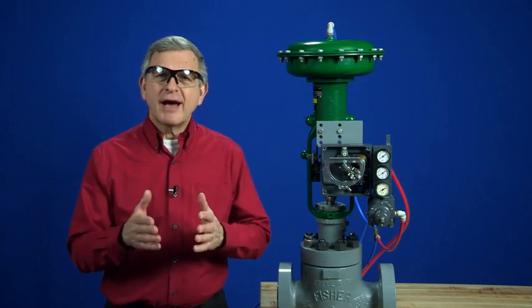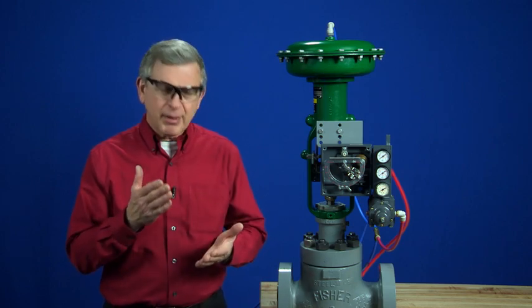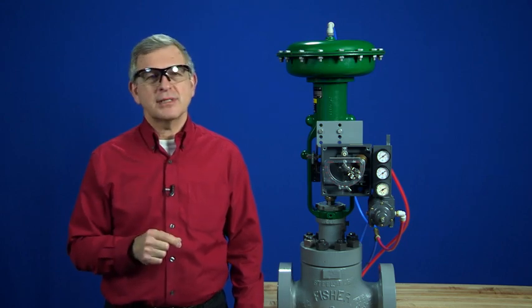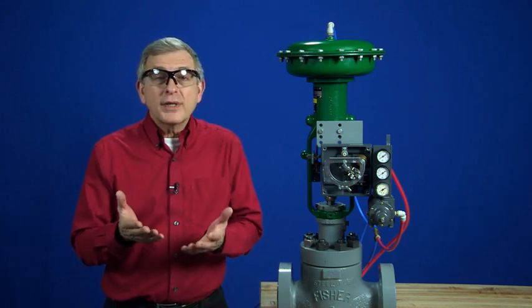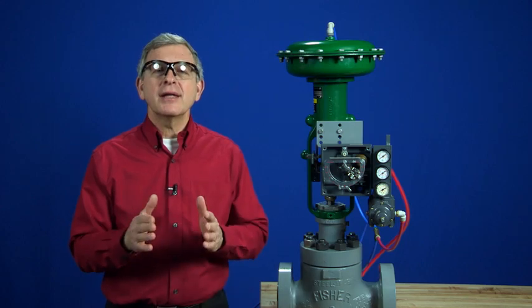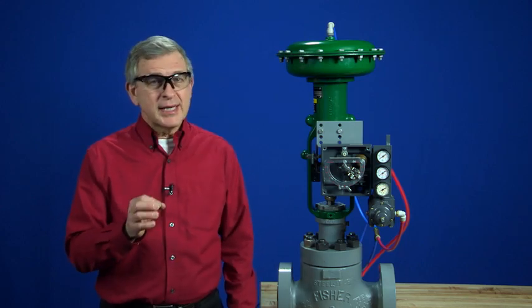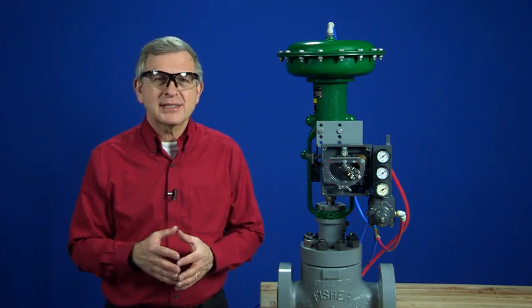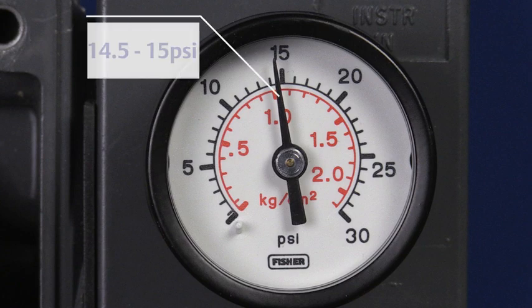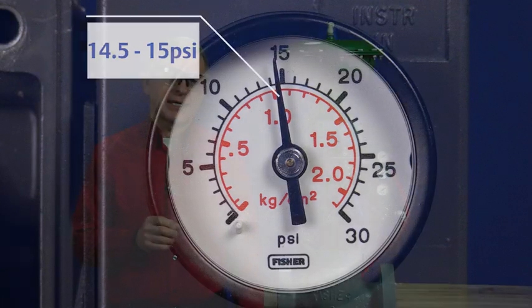That means the valve has hit a stop, and the positioner is applying full supply to provide maximum seat load. Our goal is to make the positioner saturate just inside the upper limit of our input signal, in this case, 15 psi. When it saturates, ideally, it should be between 14.5 and 15 psi.